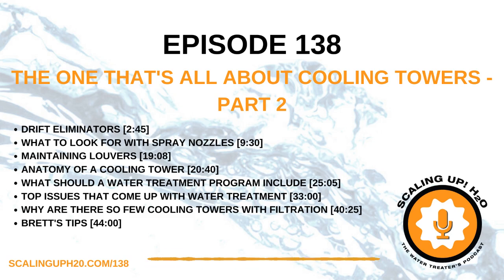Because the modern ones are now down at 0.001% to 0.0005%, where the older ones could be only at 0.01%. So, a significant difference. Upgrading to the new modern drift eliminators can really help keep that water inside the tower. If you're up there looking at the drift eliminators, you definitely shouldn't see any algae or anything on the top. You shouldn't see any wetted surfaces.